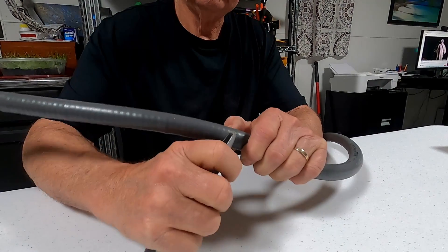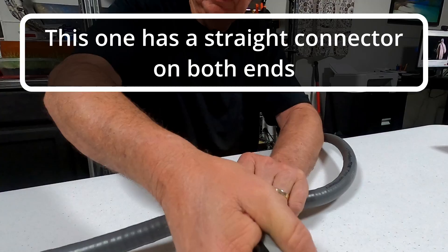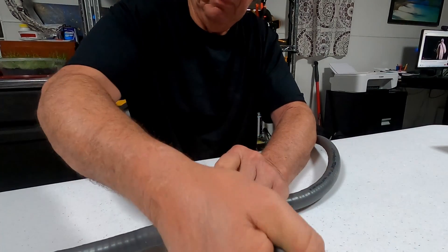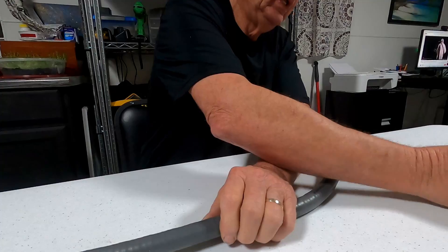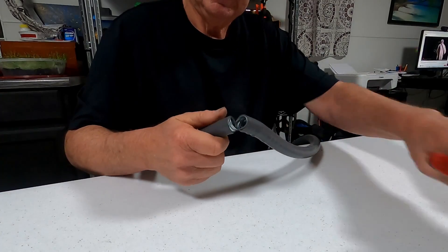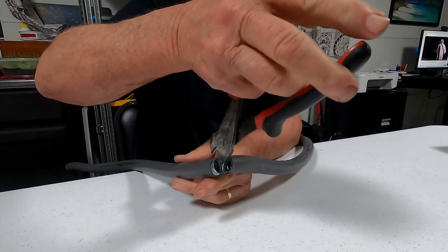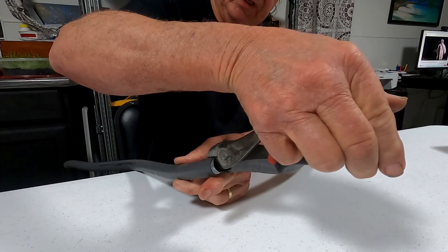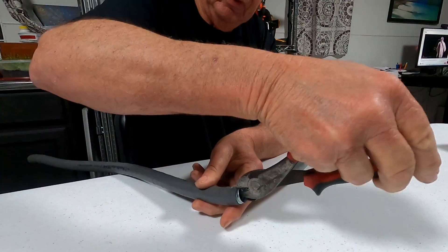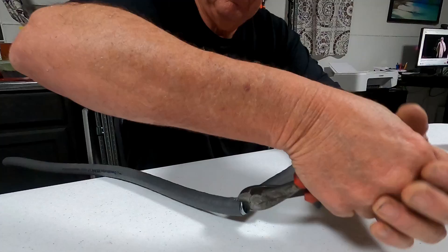I'll show you how I cut a liquid-tight metal-lined flexible conduit. First I take a razor knife and cut the plastic insulation on the outside. You can cut this with a hacksaw — many people do it that way — but I choose to do it a little differently. Sometimes when you're in the trenches and actually out there building something, you don't have a hacksaw with you. The tools I use are readily available in my tool pouch, so this is the easiest way to do it.